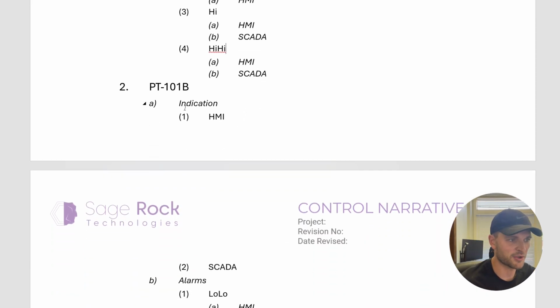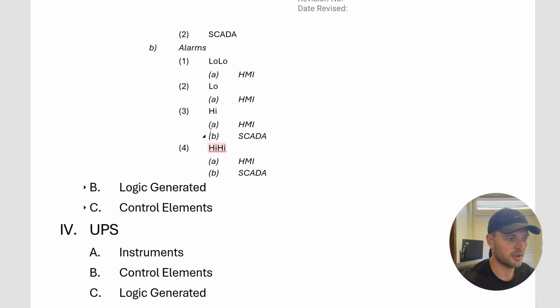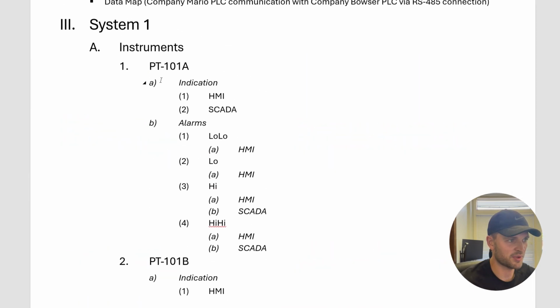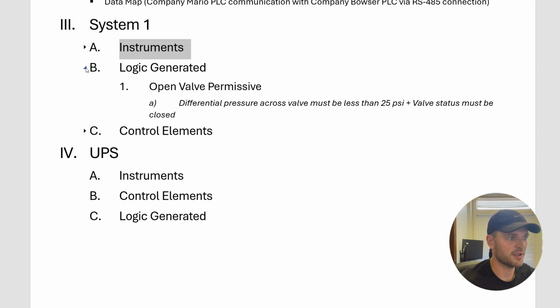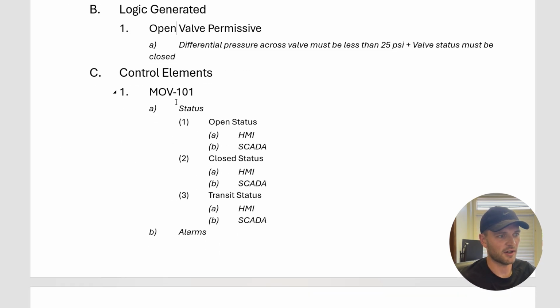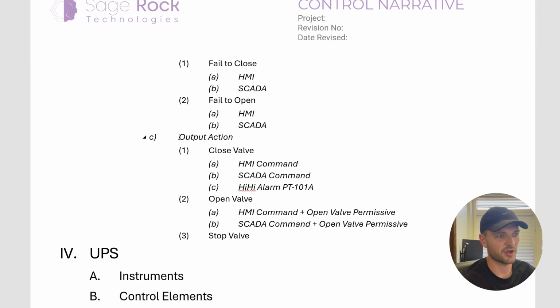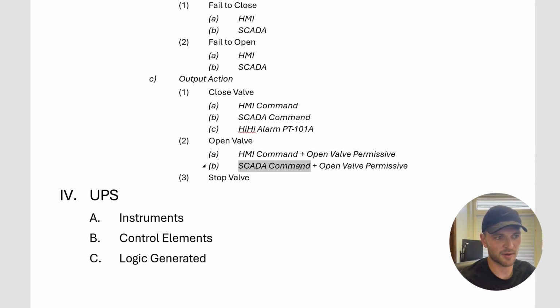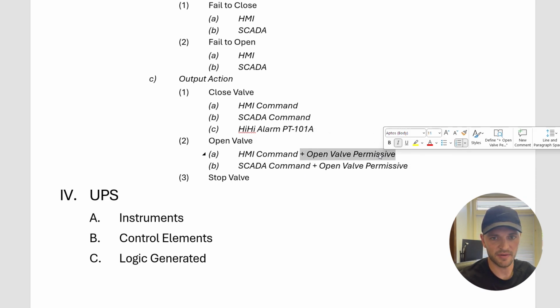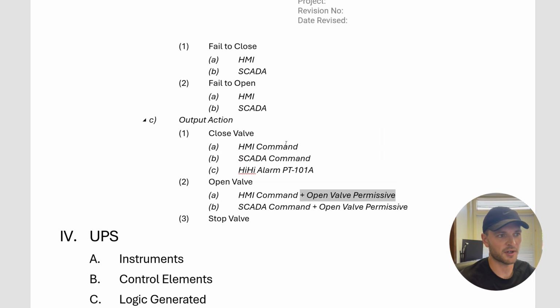Same exact structure for my second pressure transmitter. We'll have indication, and then we'll have alarms. And it's a pretty simple system. So those are our inputs. For our outputs, okay, so we'll have an open valve permissive, right? So this will be our differential pressure across the valve must be less than 25 psi, and our valve status must be closed. So that'll generate a valve permissive. As you can see in our control element, in our output action, in order to be able to open the valve, we must have an HMI command or a SCADA command plus that open valve permissive. So it essentially becomes another input to our control element.